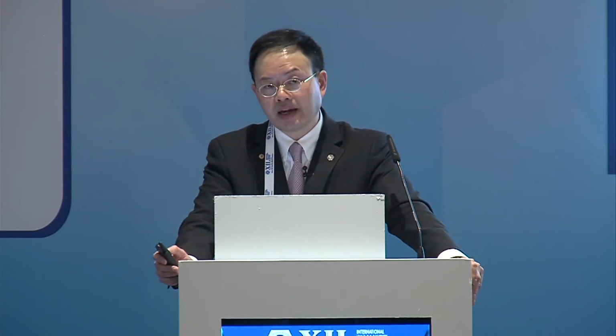In the US, we also utilize the blower door to test air tightness, not just for healthcare facilities, but also for residential, commercial, and clean room spaces. In the US and Canada, we have ASTM and Canadian standards. You can use a computer to calculate the equivalent or effective leakage area.